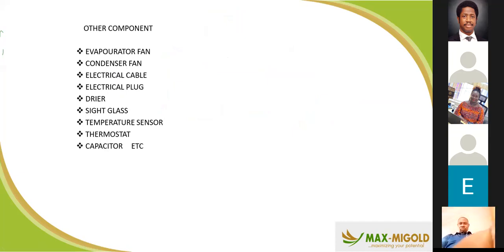Most buildings have been burnt down because of electrical cables. Because when they bring light on, the AC starts up, and because your electrical cables are fake, there's every tendency that fire can break out. Then your electrical plug: every AC goes with a 15 amps plug, not 30 amps. People take risks using 30 amps, but it's not advisable to use it. Then for a bigger system, we have a dryer.